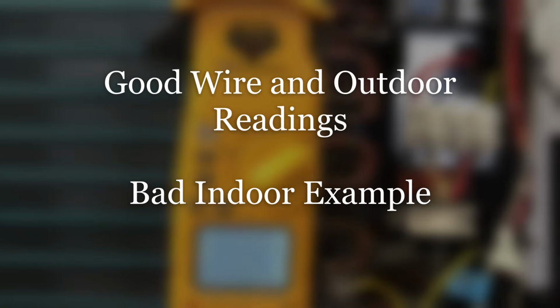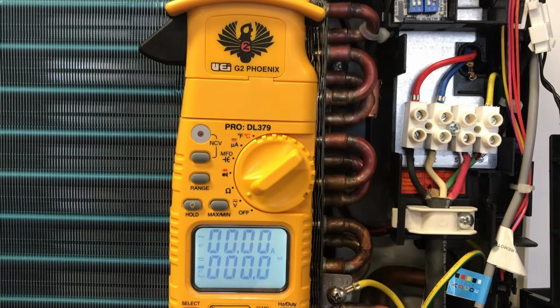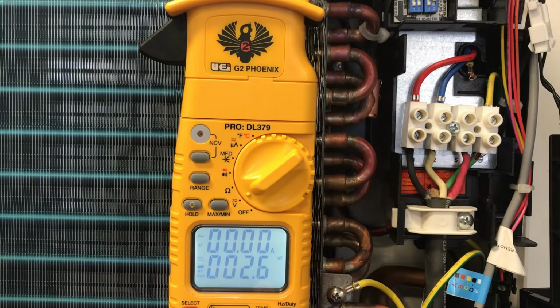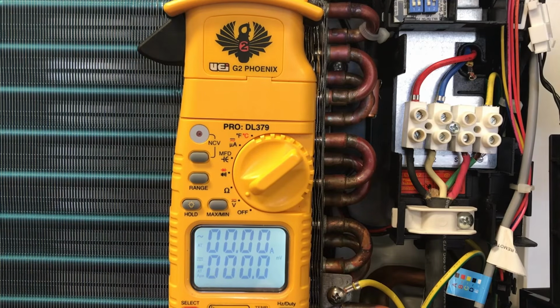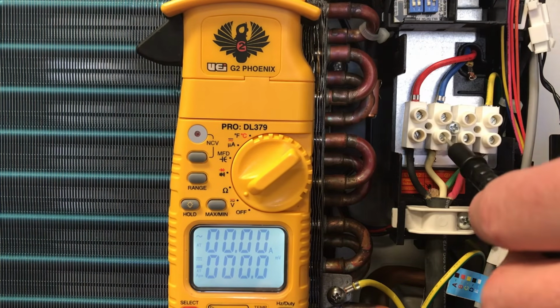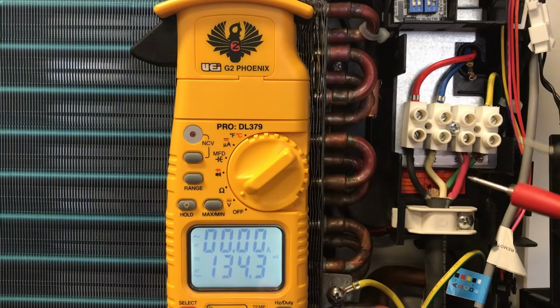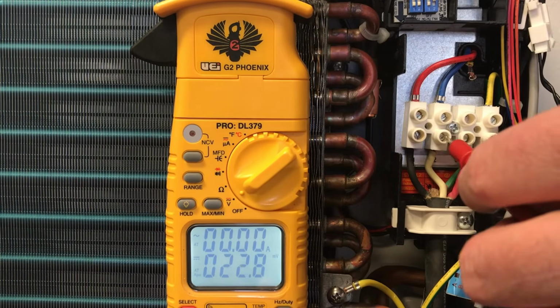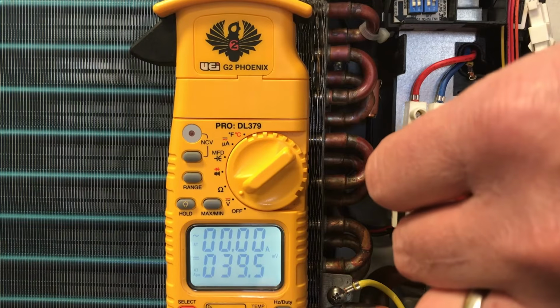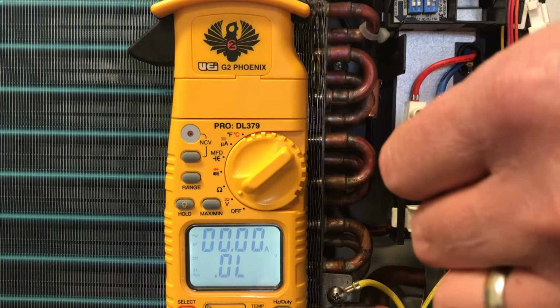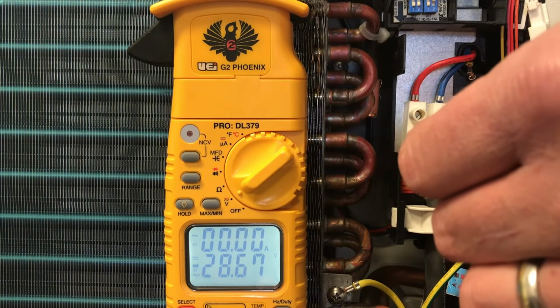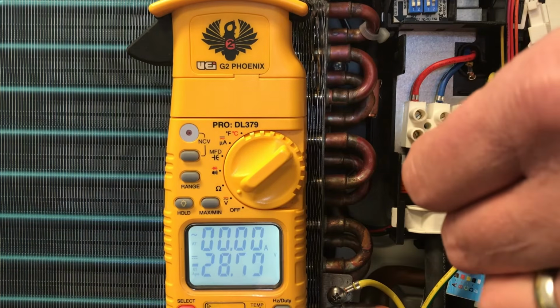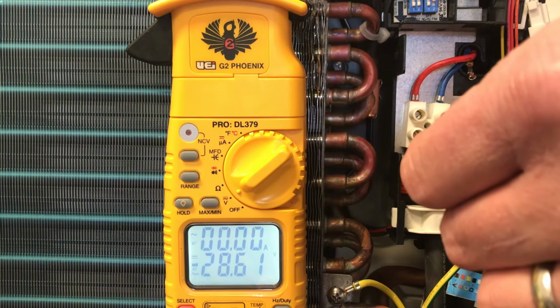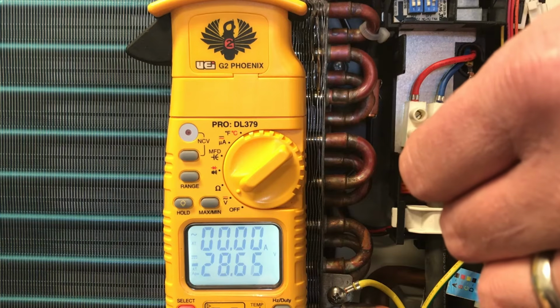All right, now we just showed you what it looked like when we possibly had a wire issue with a communicating problem with the indoor unit, but now we're going to check it out with a possible board issue. So we're going to check our leads once again to L2 and S. Once again, make sure you use the right leads. Almost made a mistake there. Red's going to go on L2, black's going to go on to S. And as you notice, it's now back to a negative DC voltage, steady and not fluctuating.